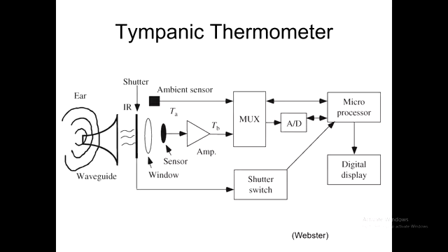The other method that's of interest to us in the clinical domain is the pyroelectric type sensor-based systems that are typified by the ear thermometer, and most people would have used one of those or seen them used in clinical settings or in the home even.